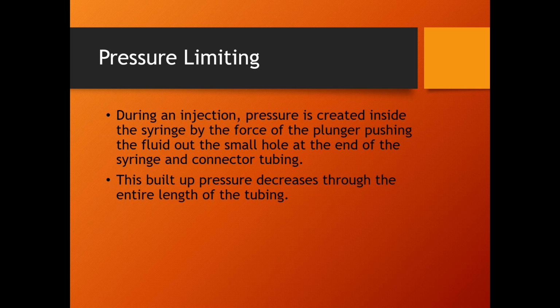Pressure limiting. So to go into a little bit of explanation, all right? Are you BMAT or, okay. Whenever we're doing an injection into a patient, there are three things that the operator has to program into the injection: flow rate, volume, and pressure limit. Flow rate is how fast we are going to inject this fluid into the patient. It's always in milliliters per second. The typical injection is 3 to 5, 6, 7 milliliters per second. The other thing they have to program is volume. Not how fast, but how much fluid we are going to inject in the patient: 40 milliliters, 60 milliliters, 120 milliliters. So those are the two main ones.